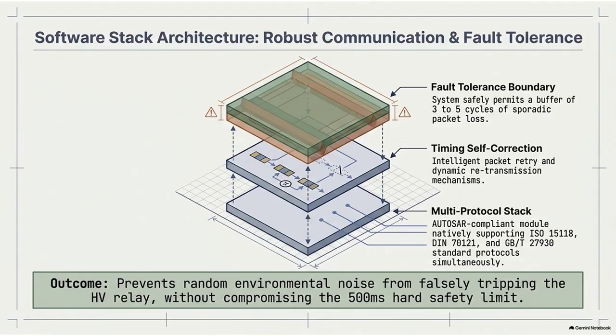What about the anti-bounce RC filter? You mentioned that when metal contactors close, they physically bounce, creating high-voltage sparks. Does the plug do that too? Absolutely. When you push the heavy charging plug into the port, the metal pins don't just perfectly connect once. At a microscopic level, as you push, the metal surfaces scrape, connect, disconnect, and bounce against each other dozens of times over a few milliseconds before finally settling into a firm connection. To the computer, that mechanical bouncing looks like a chaotic, rapid-fire machine gun of electrical noise. The computer might interpret that bouncing as dozens of separate plug-in events, which could crash the state machine software.